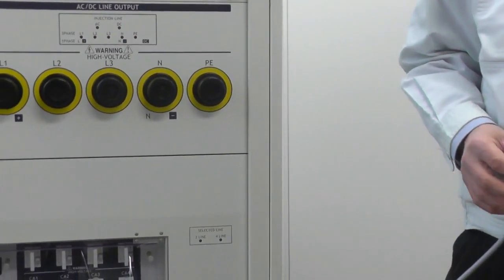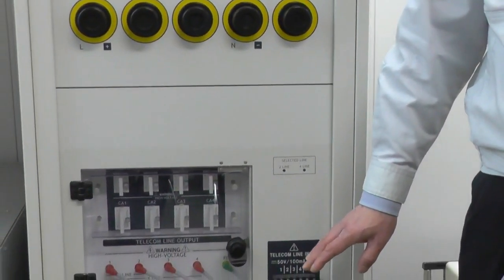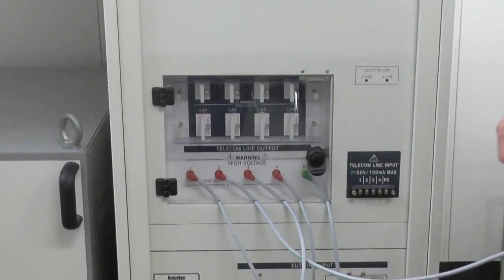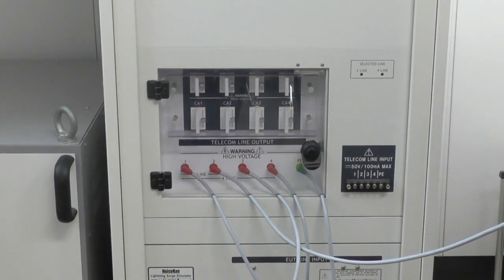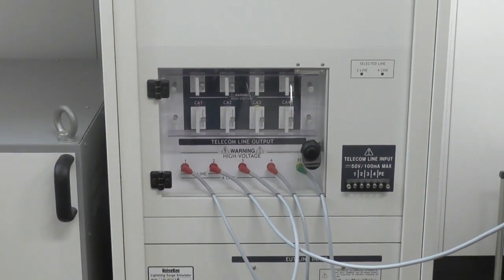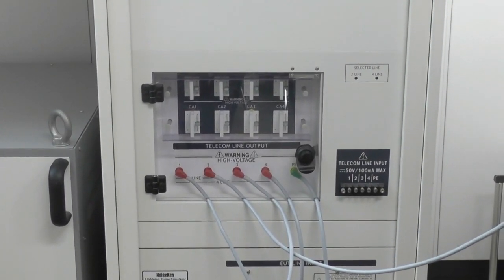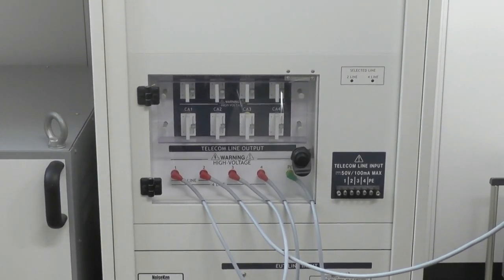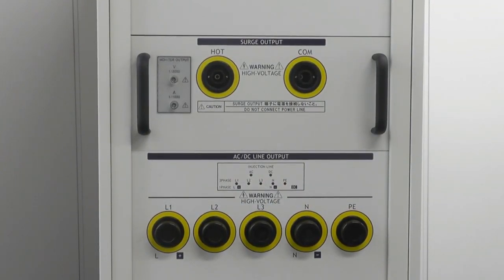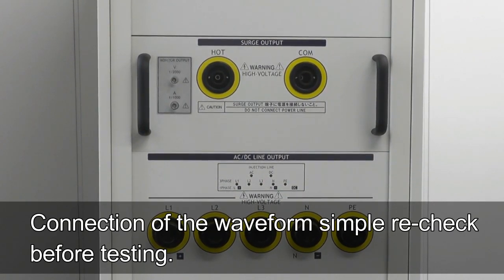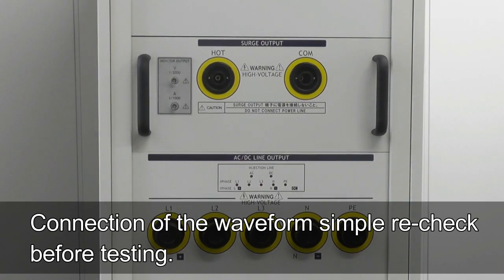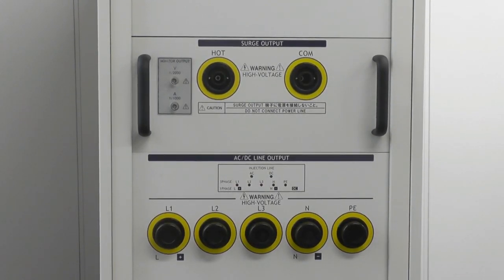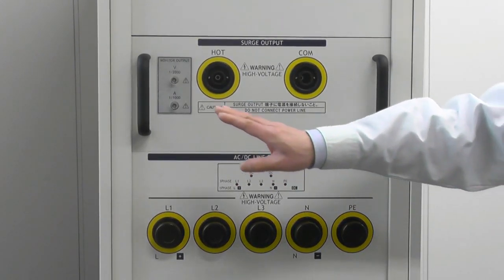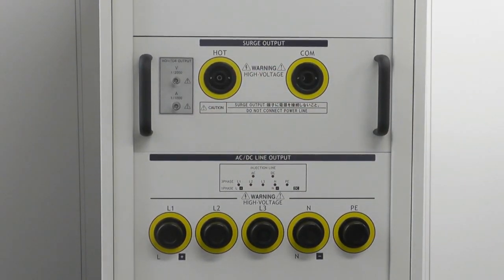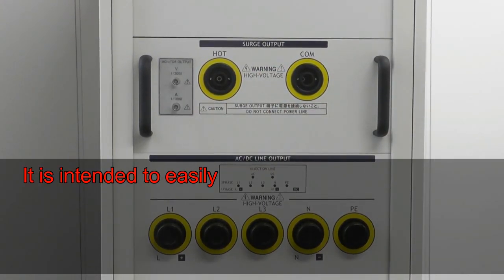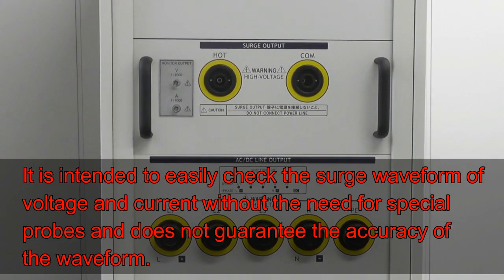And please keep in mind that the high voltage surge outputs from those terminals, incorrect or careless operation may result in serious injury. So be very careful. In response to the request for a simple check of the output waveform before testing, this lightning surge simulator is equipped with monitor terminals. All you need is an oscilloscope and an oscillation transformer.